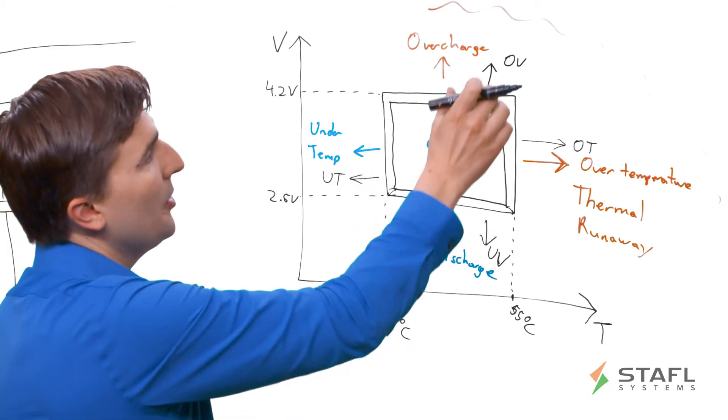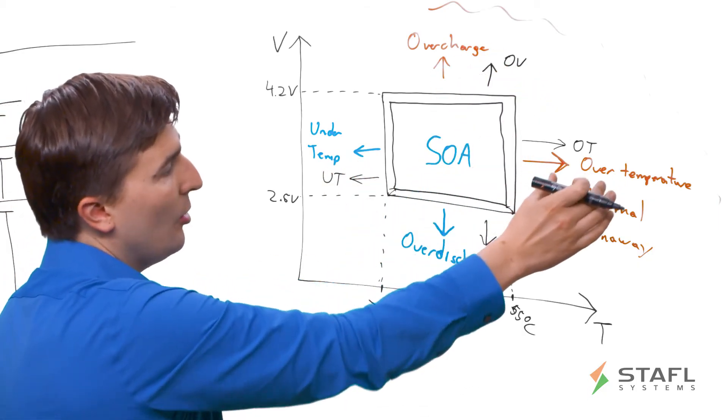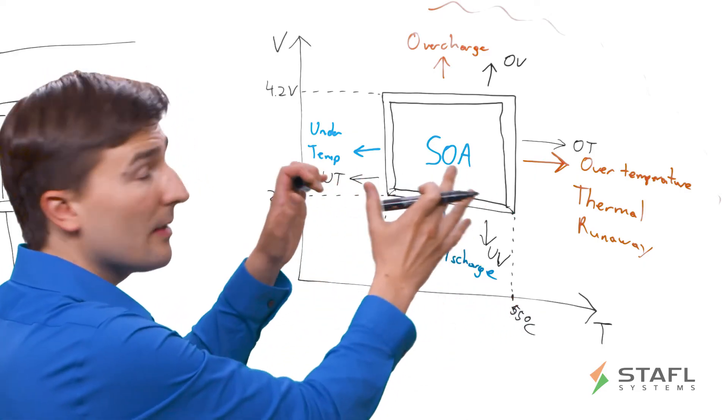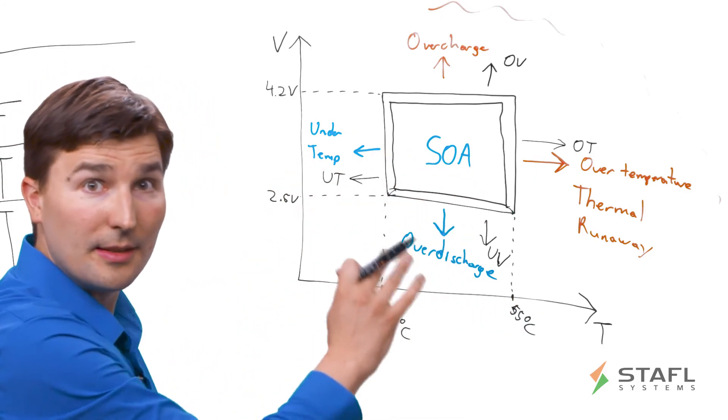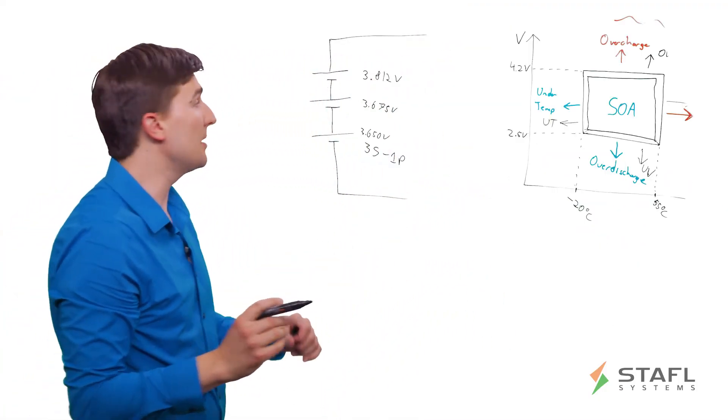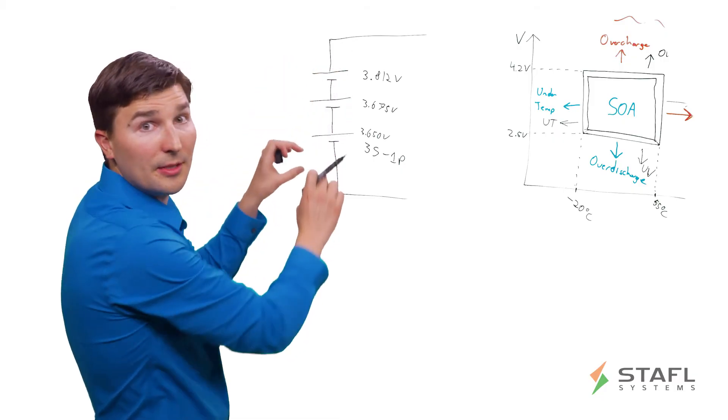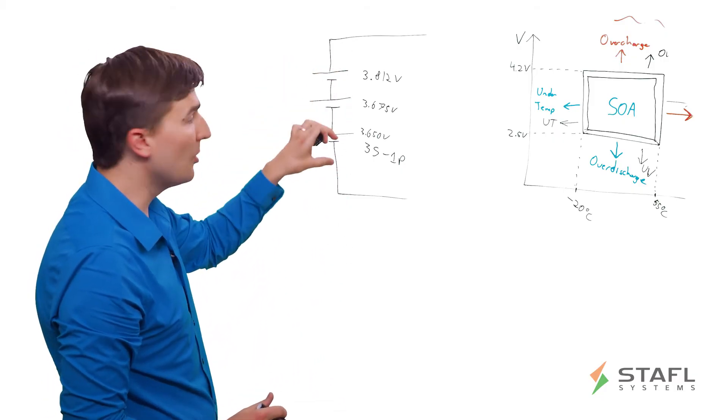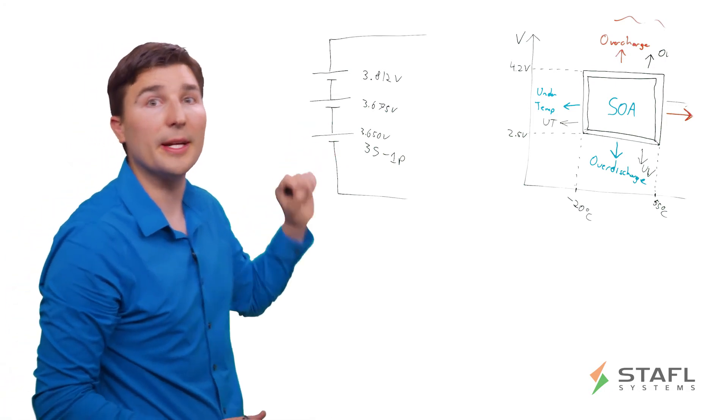And so you can have cell OV, cell OT, cell UV, and cell UT faults. And this, remember, this has to be for every single cell in the system. So you can't just look at a single cell and assume that it's going to be safe. You have to look at every single cell. And if one cell is getting too hot, too overcharged, too over-discharged, you need to shut down or derate operation of the system.